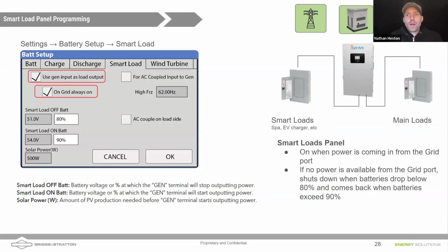So what we can do is we can always have that sub panel on if the grid is there, but there might be some loads you just don't want to back up in a grid outage, right? And that might be things like a car charger. Don't necessarily want to be draining your home battery so you can charge your car up, right? You might want to put that water heater on there. If you have an electric water heater, you might want to have an air conditioner on here, right? Maybe have small window units on the main load center, but have that big whole home air conditioner on a load shed panel. And so if the grid is up, if you have that box for on grid always on checked, then that sub panel would always be on if grid utility power is available.